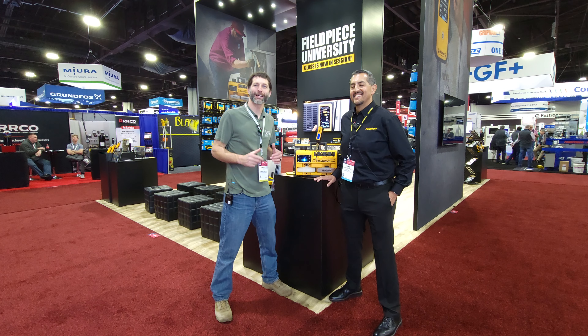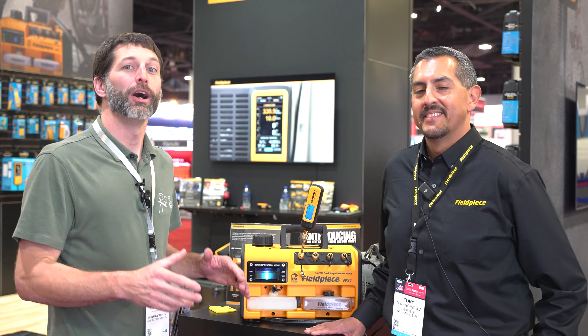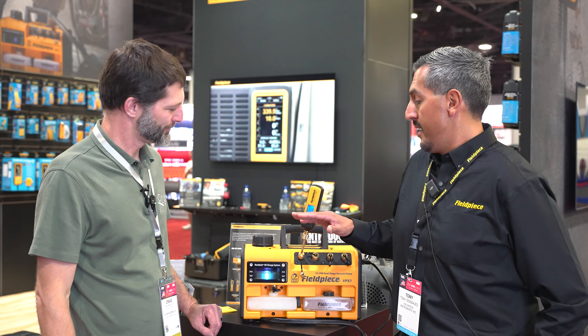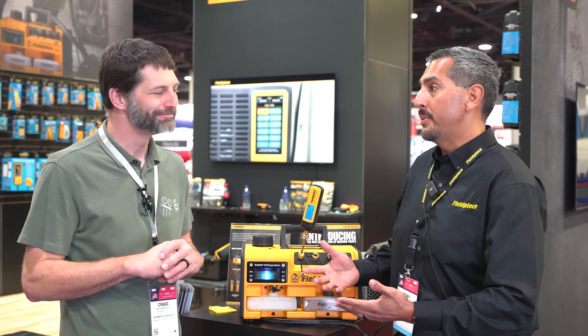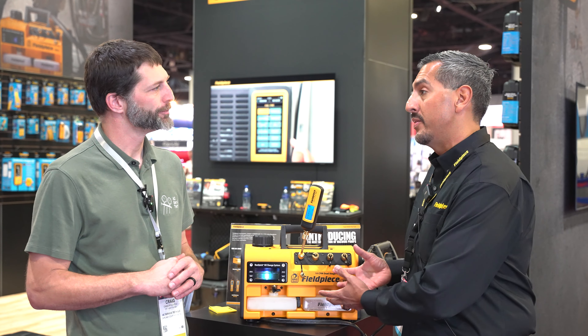We're here at AHR 2023 at the Fieldpiece booth and Tony is going to talk about the importance of having fresh clean oil in your vacuum pump. So one of the common misconceptions in the field is a lot of people think that the purpose of the oil in the pump is to collect moisture from the system, but that's not the case. Its purpose is to provide lubrication but also to help maintain a tight seal within the pump.